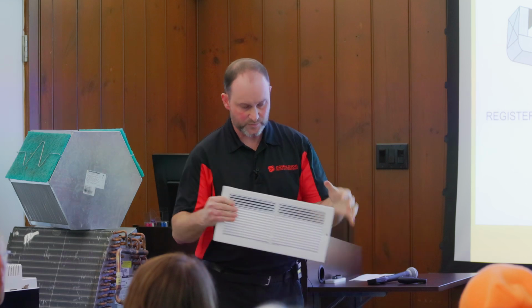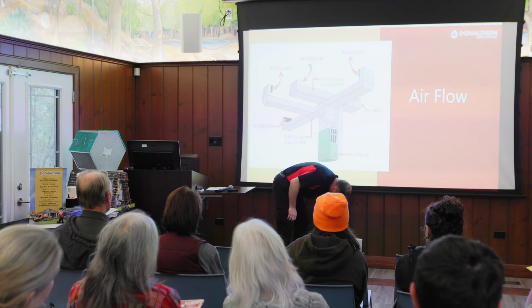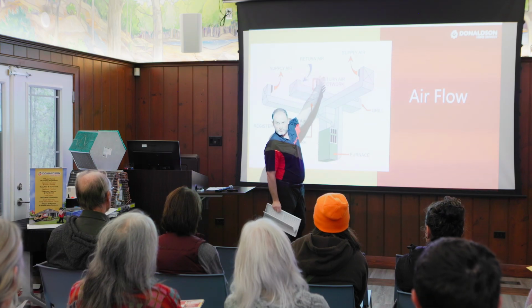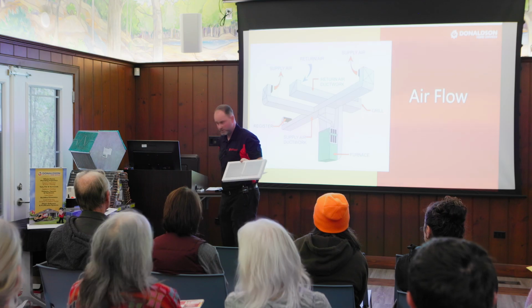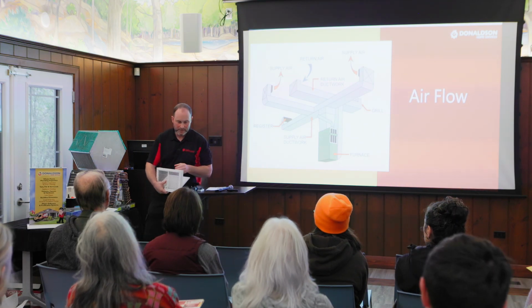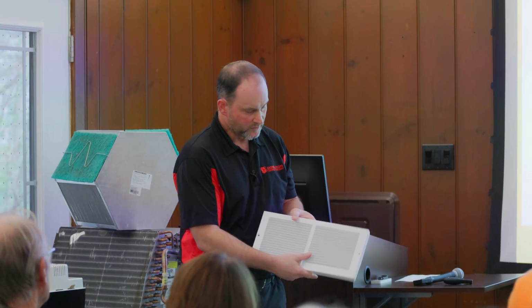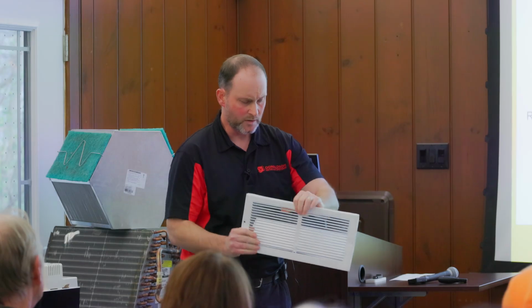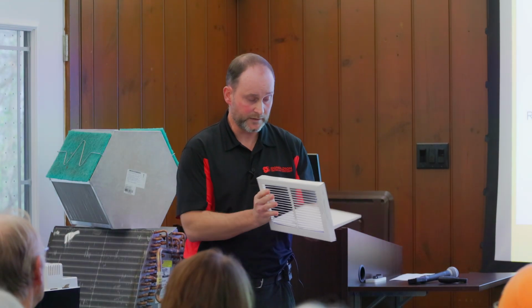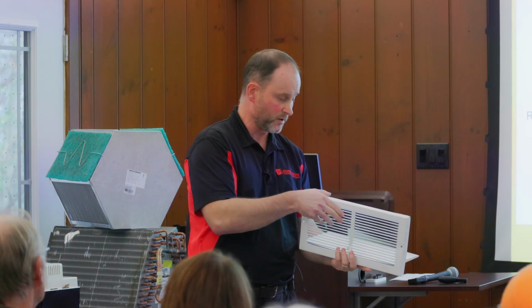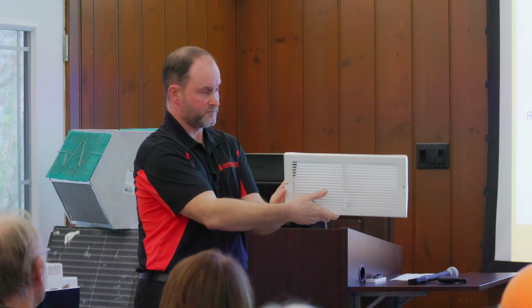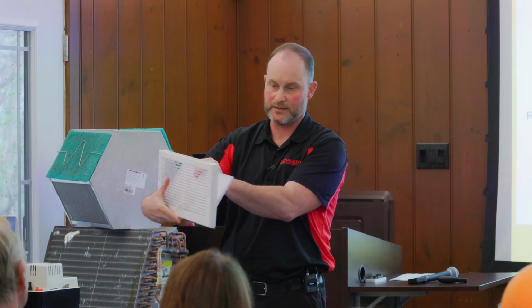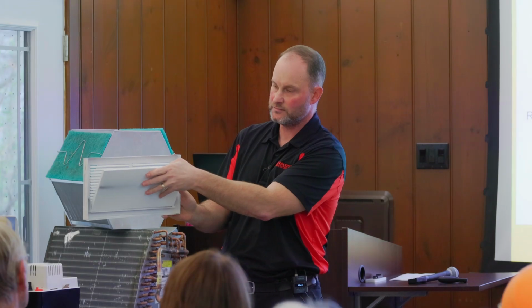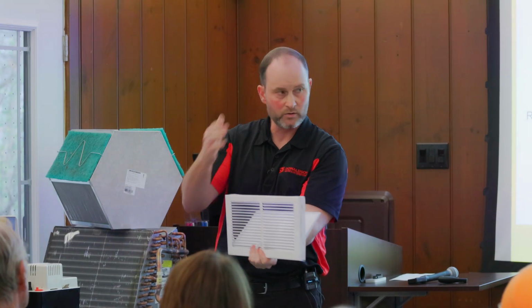How many of you have seen this before? The return air would be down low on the floor, and then you'd have another one up high, right directly above it, but no damper in it. Here's the trick, and often this isn't being done in homes: there's a damper here. When you're heating, you want the damper positioned so that it draws cold air off the floor in the wintertime — that addresses complaints about cold feet — it'll draw that cold air through and keep you comfortable.